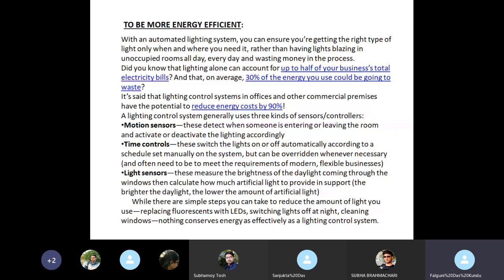Motion sensors detect when someone is entering or leaving the room and activate or deactivate the lighting accordingly. Time controls switch the lights on or off automatically according to a schedule set manually on the system, but can be overridden whenever necessary to meet the requirements of modern and flexible businesses. Light sensors measure the brightness of the daylight coming through the windows, then calculate how much artificial light is needed in support. The brighter the daylight, the lower the amount of artificial light required.